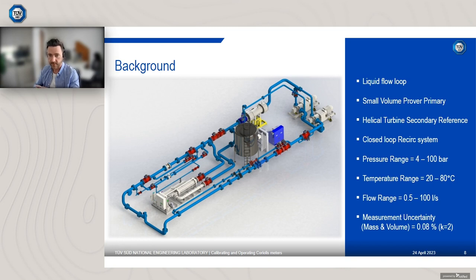In terms of temperature stability for a calibration, we can certainly achieve in the region of 0.25 degrees Celsius over an entire calibration as well, simply by tweaking the settings on our heat exchanger to maintain the temperature at the required set point. The flow range, we operate from 0.5 to 100 litres a second. As I say, we have 3 separate master meter systems. And the measurement uncertainty at k equals 2 for mass and for volume is 0.08%.